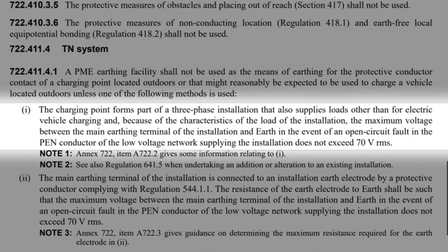It states that the charging point forms part of a three-phase installation that also supplies loads other than for electric vehicle charging, and because of the characteristics of the load of the installation, the maximum voltage between the main earthing terminal of the installation and earth in the event of an open-circuit fault in the PEN conductor of the low voltage network supplying the installation does not exceed 70 volts RMS.